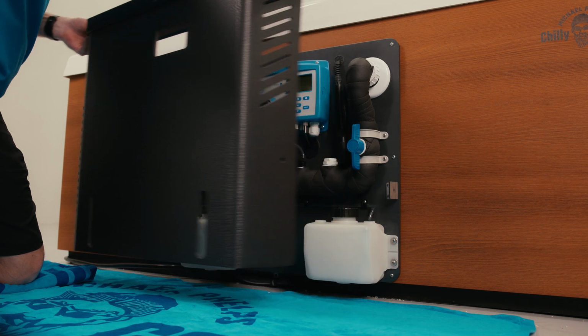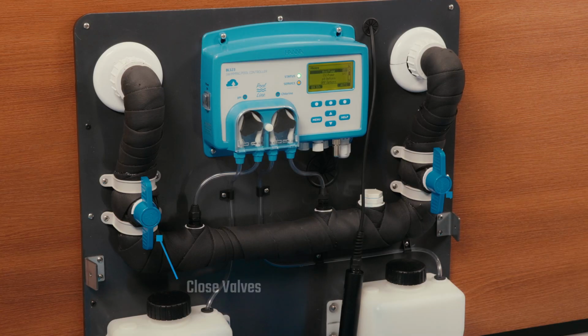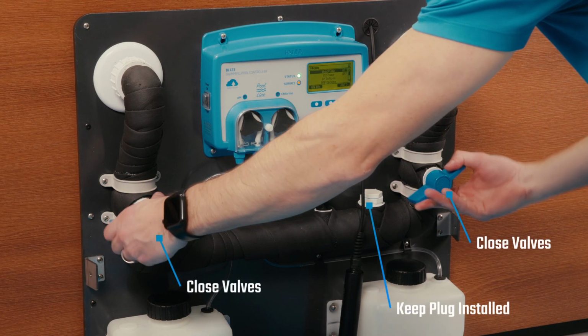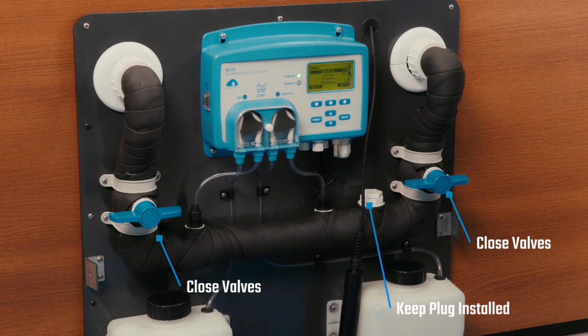You'll see the valves feeding the probe are in their open position for normal operation. Start by closing the two valves to stop water flowing through the probe port. Next, you will see that there is a probe plug pre-installed. Keep that plug installed for now, as it is needed for the calibration process.